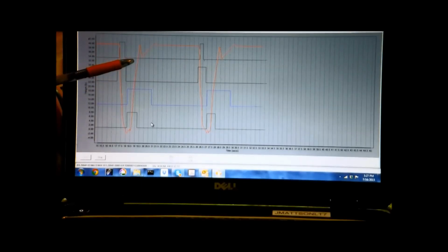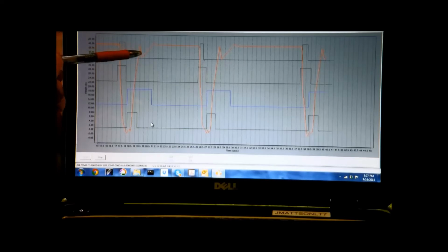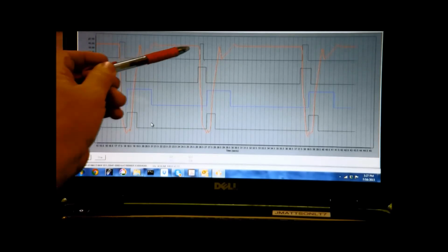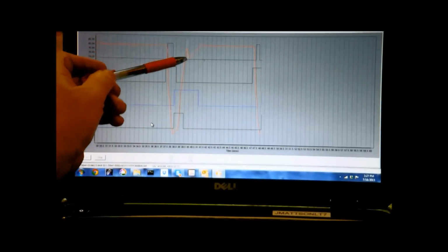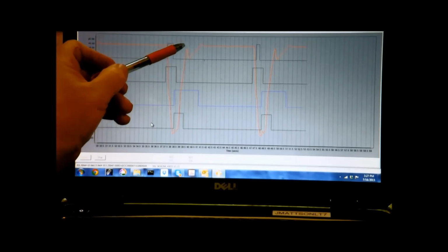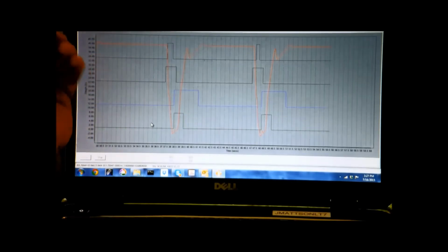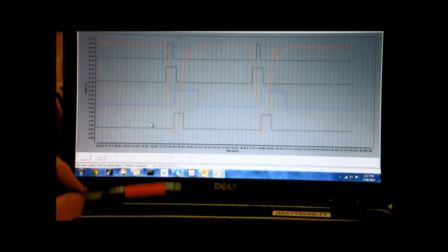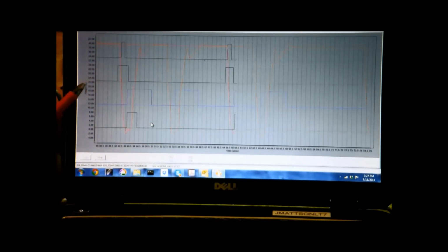Basically, this is showing each input and output being made, but the red line is showing our spike time, and then we calm down till we get to our final weight, discharge, restart, spike. This is the important part to watch. If we were to come above our target, we would stop, and when it calmed down, every bag would be overweight. The machine can compensate for that only to an extent. So this is a good diagnostic tool.